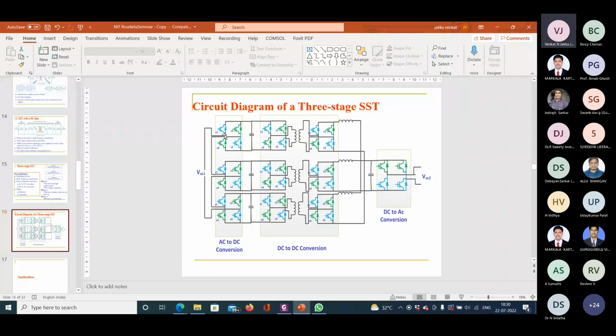So what you can do is provide charging before utilizing them, or use a high resistance path at the primary side before charging. Once it is charged, you bypass that path and connect directly to the supply. Also, even when stopping, charge can remain stored across the capacitor—you will see the voltage, and you need to discharge it.